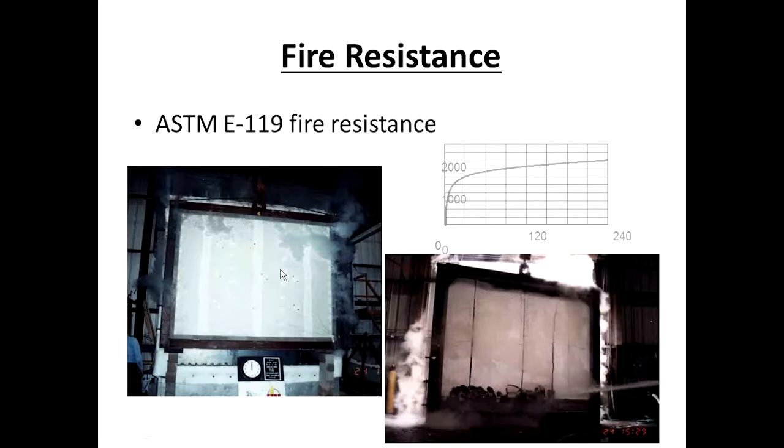That concrete steel yoke is then clamped in front of the furnace, and a fire is started. This fire source was typically here in the United States natural gas. Almost all of it's natural gas here in the United States. I did have the opportunity in the mid-90s to go to mainland China, and we had to run fire tests to qualify for a project there. There we ran into an oil-fired furnace and huge learning curve on it.